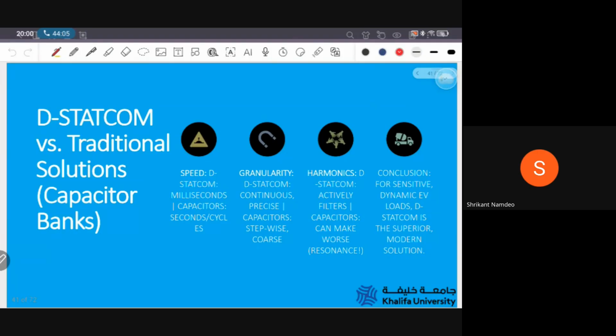So D-STATCOM is fast, precise, and immune to resonances. And capacitors also cause resonances. When we are installing inductive equipment or motors, we have to evaluate the total capacitance at the point of common coupling to avoid resonance and high inrush currents. For dynamic EV loads, it is the superior modern choice. That is nothing but D-STATCOM.